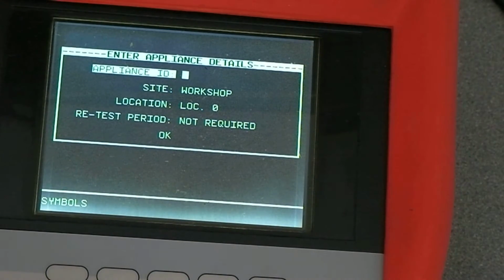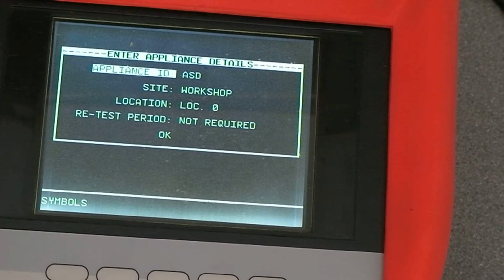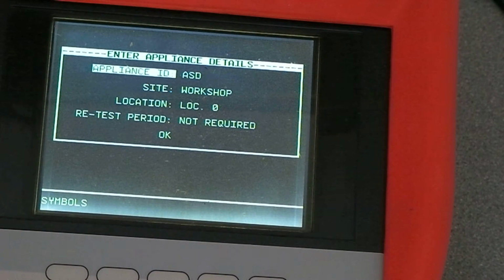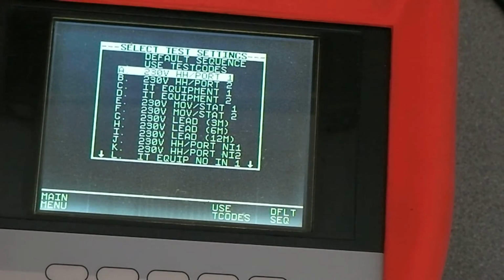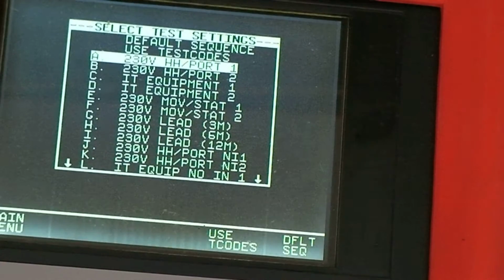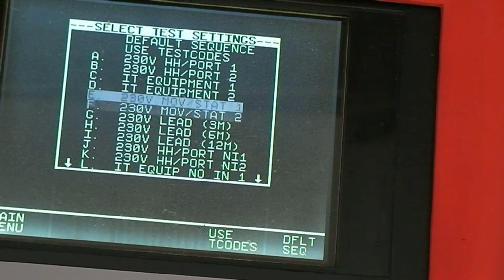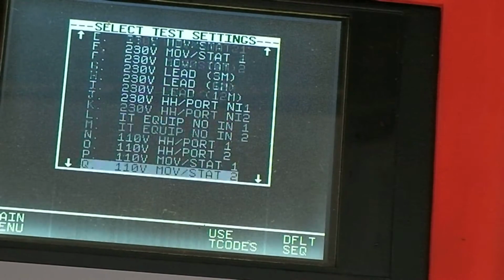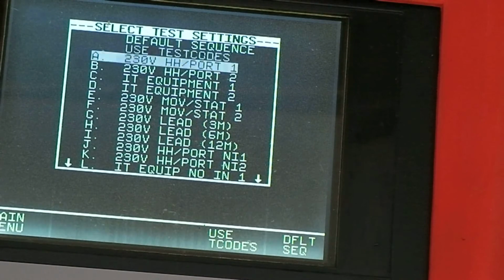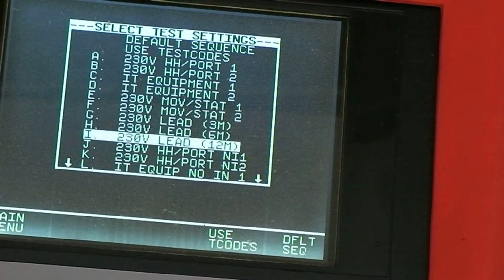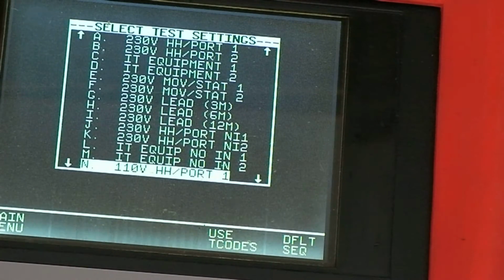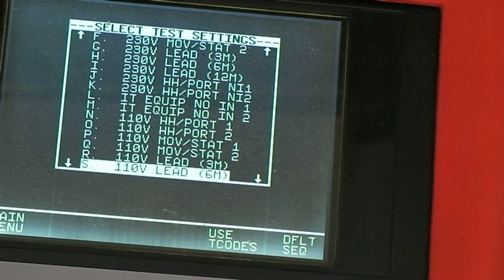I'm not going to enter this. Let's see if it will skip without entering that. Yeah, it will. No, it won't. I'm going to have to make up something. So let's make up an appliance ID. Press yes on the touch keypad, then OK, and then you have the whole list of tests that it is able to perform. Hopefully this is in focus for you guys. It's a bit tricky. So you can just use the cursor keys to select whichever test that you want, and this will do all sorts, from 230 V IT equipment, down to mains leads, and also 110 volt equipment.